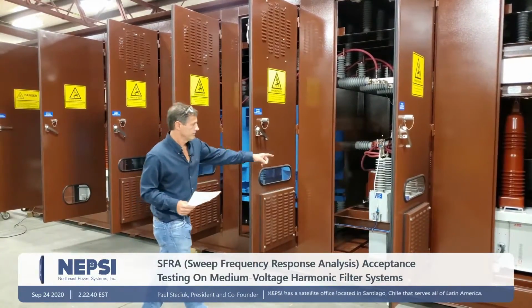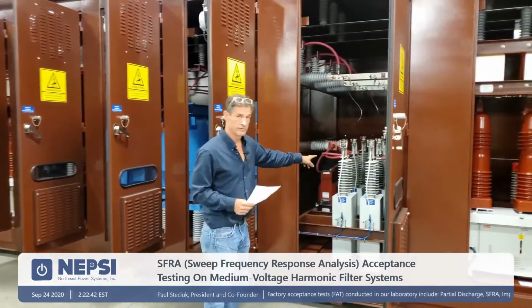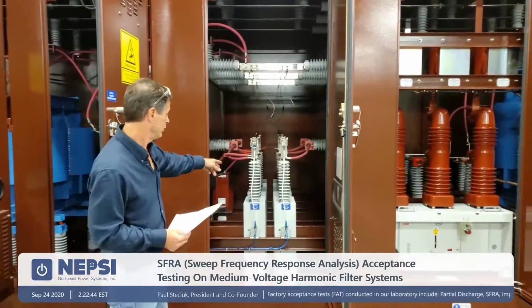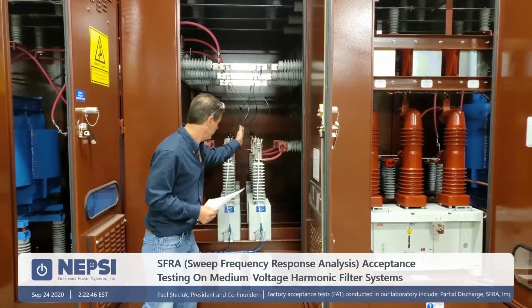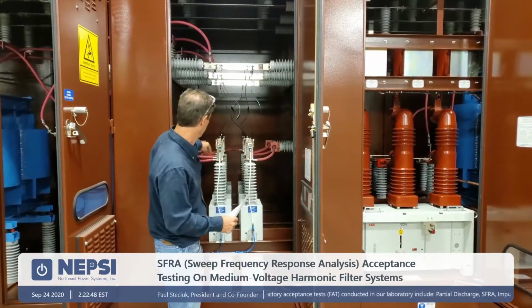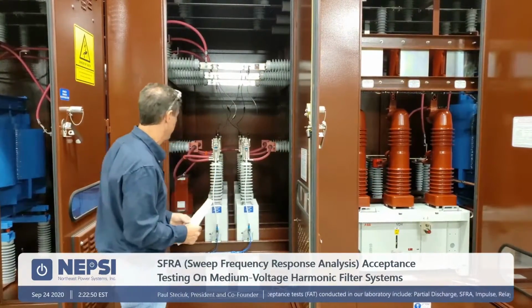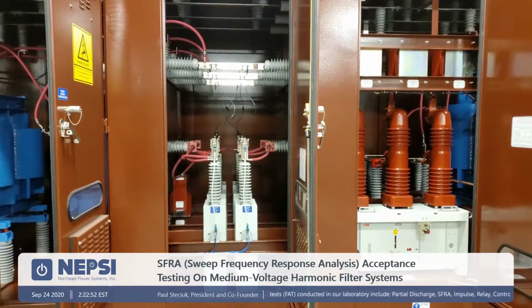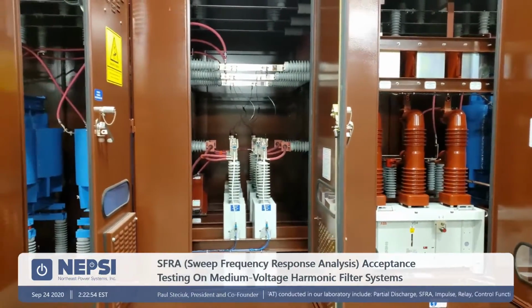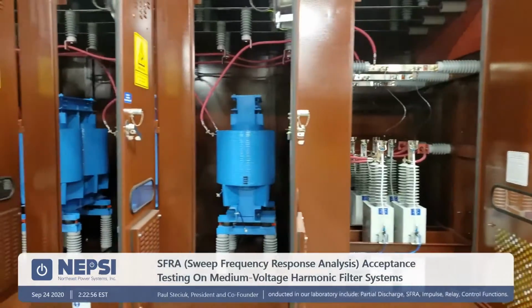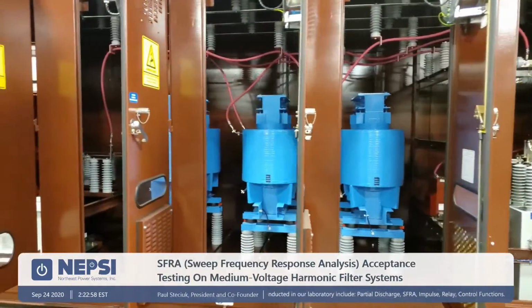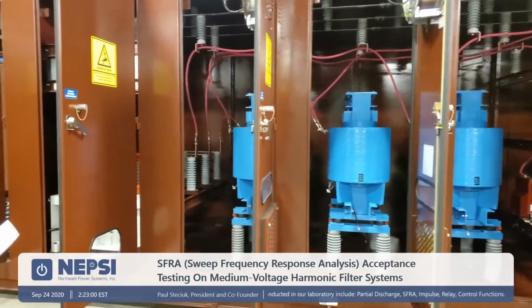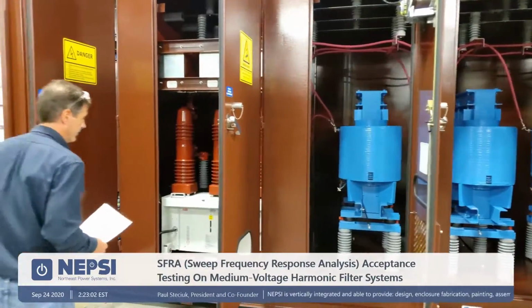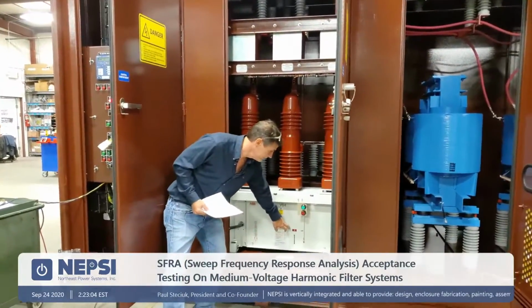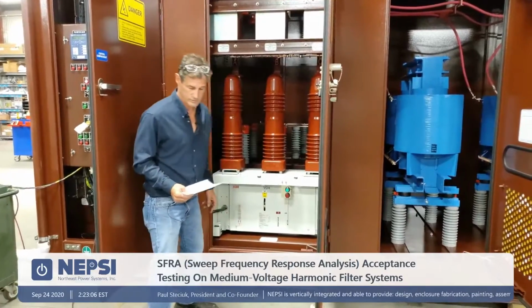So moving on, just the stage 1, it only has 2 caps. That's half the size of stage 2. And again, split Y right down the middle. There's no connection between, but only through the Y point. And these reactors are quite a bit smaller than the other reactors. And again, this breaker is closed.